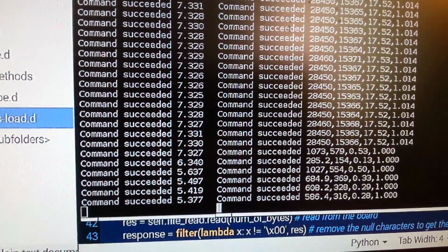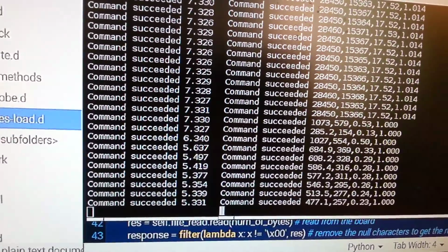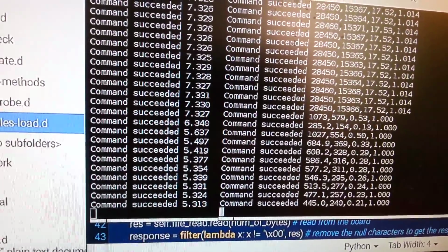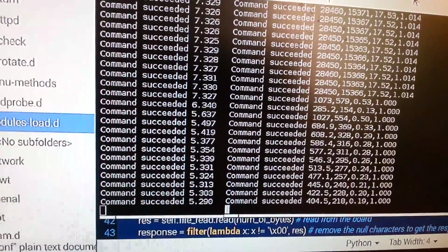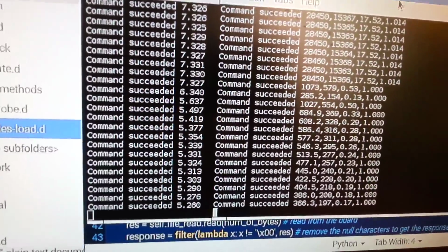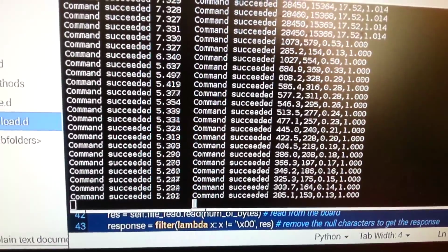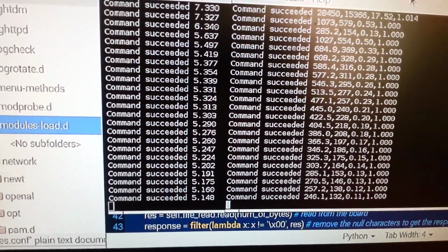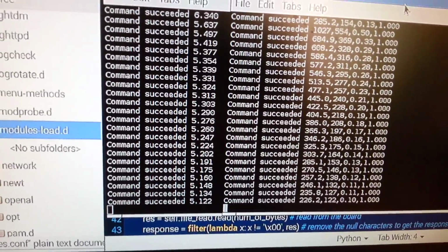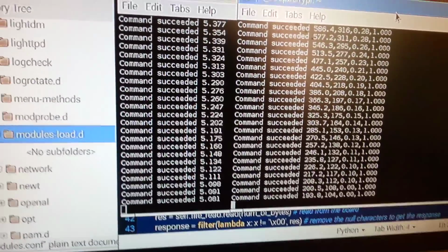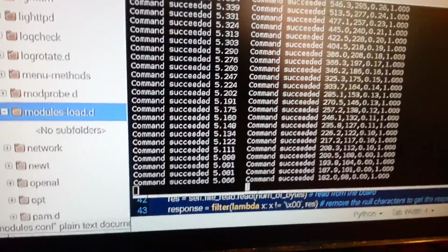Yeah, okay, so you can see there the pH change, which is on the left. It went from about 7.325 to about 7.3. Well, no, it's coming back down. It's actually going low now. So the EC probe did indeed affect the pH probe. And over here you can see the EC probe is dropping way down. Everything is going to null out to zero because I am using RO water in that cup over there. And now my pH is just going crazy. It's because that EC probe is inducing a current. So that's going to be a problem.